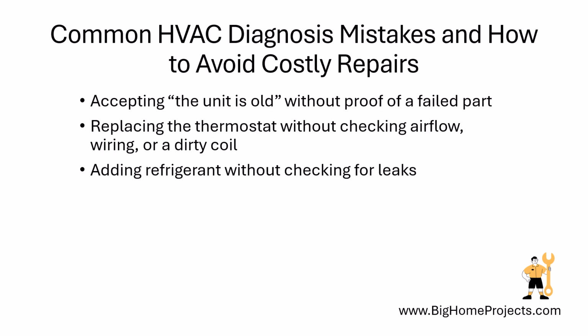One common mistake is accepting "the unit is old" as a diagnosis, so ask which part failed and what test proved it. Another mistake is replacing a thermostat when the real problem is airflow, wiring, or a dirty coil, so have the complete system checked before buying parts.